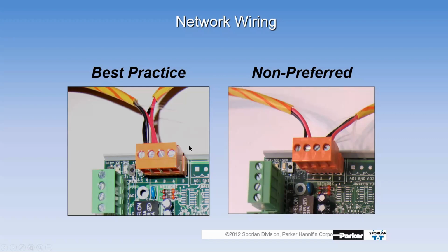Exactly right, I got ahead of myself and went to a further slide. Back in the day we had a 4-lug, and we've eliminated that on the MT700, it's only a 2-lug now. The reason, whether it's black and red or black and white, in the United States the Echelon wire is black and white, is that we physically twist the two blacks together and the two whites together, then land them on the lug. When we do that, it's as if there's no break in the black wire and no break in the white wire, are you with me on that?